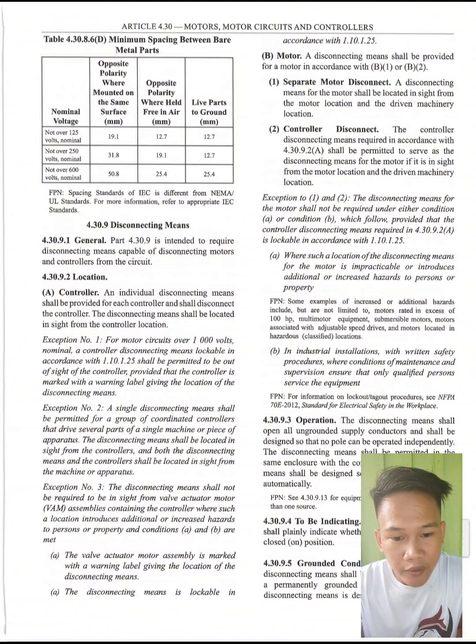So we have here the table 4.30.8.6d, minimum spacing between bare metal parts. So we have a table for nominal voltage. Opposite polarity where mounted on the same surface in millimeter. Opposite polarity where held free in air in millimeter. Live parts to ground in millimeter.